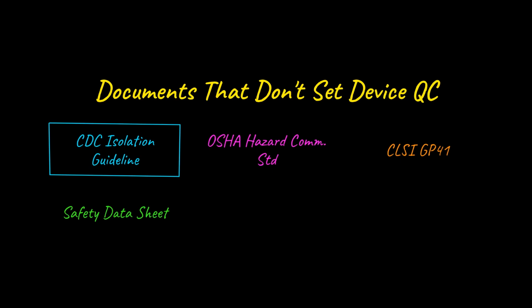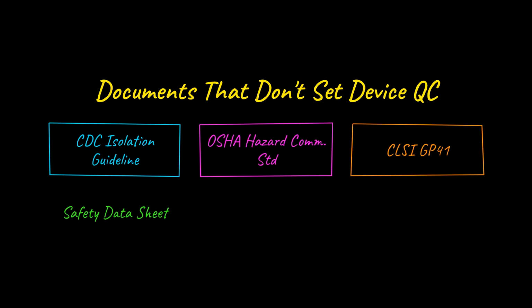The CDC isolation guideline covers transmission precautions. The OSHA Hazard Communication Standard addresses chemical labeling. CLSI GP41 governs blood collection technique. Safety data sheets describe reagent hazards. None of them set QC frequency for a clinical device. Only the manufacturer's IFU does that.